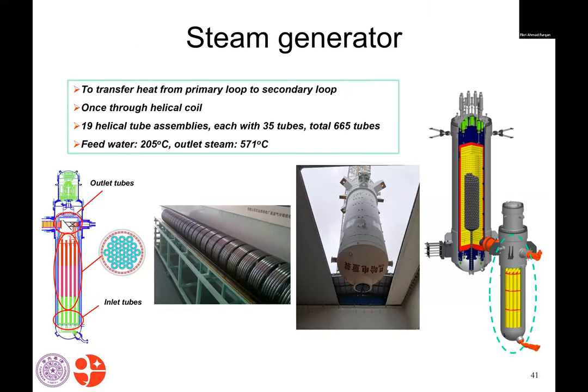For the steam generator, it's also a new design because we use 19 assemblies, and for each assembly we have 35 heat transfer tubes. We use helical coils to make that happen, which is also a challenge to us. We spent several years achieving the technology to put each heat transfer tube in position, because we don't want them too close or too far apart. It's not easy for the assembling process, but right now everything goes well.